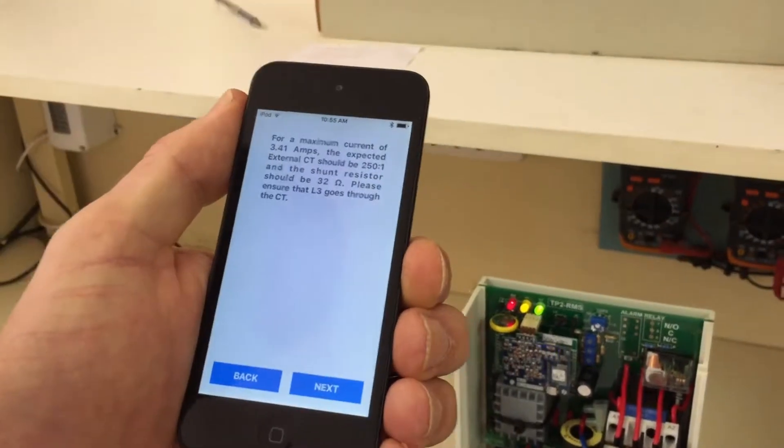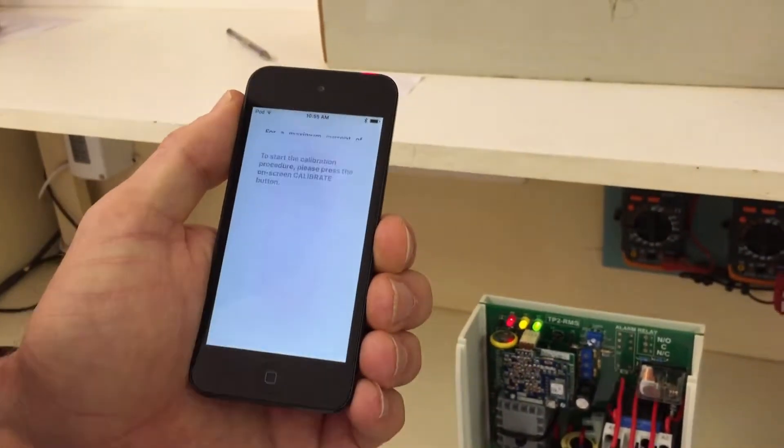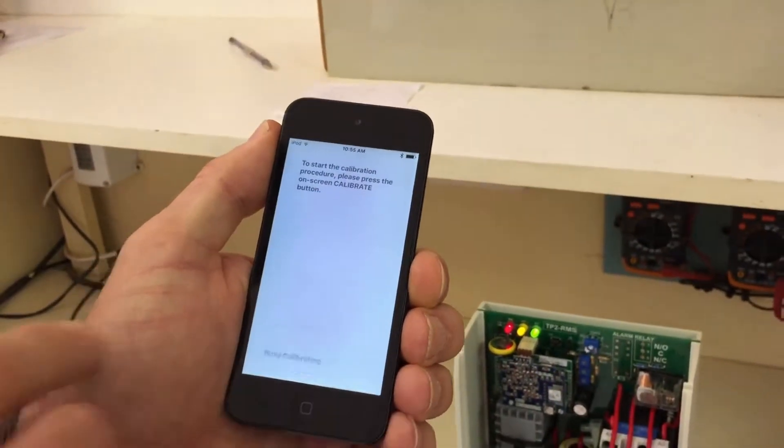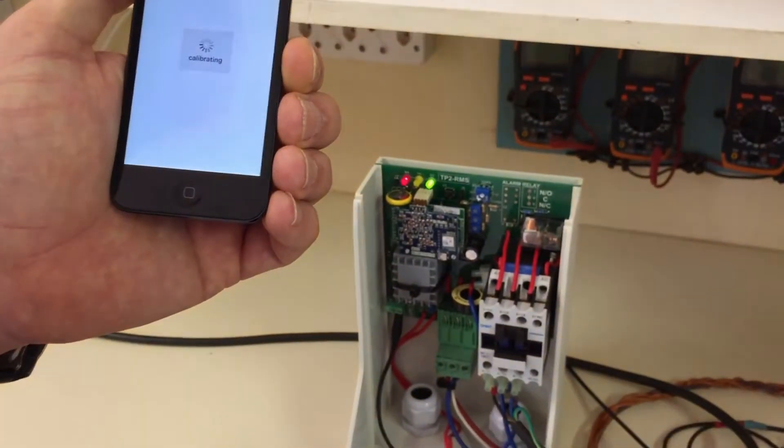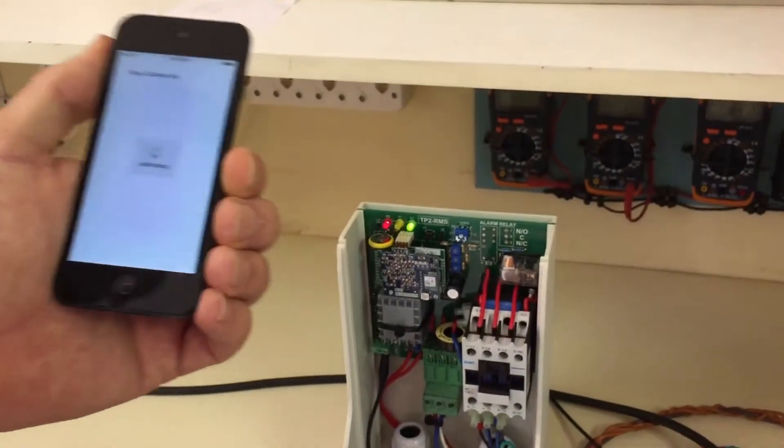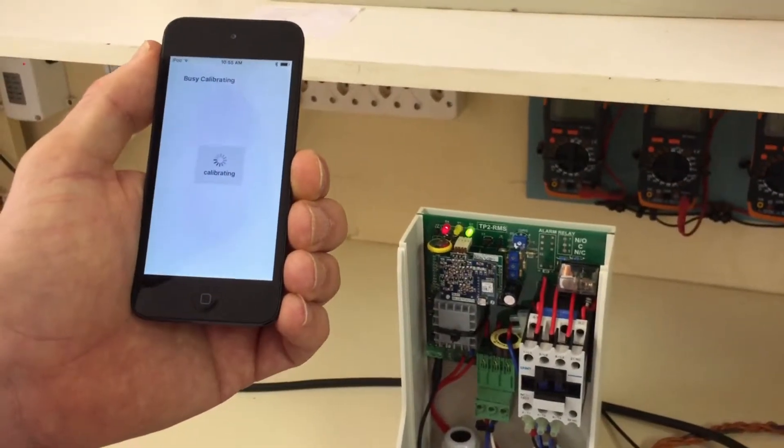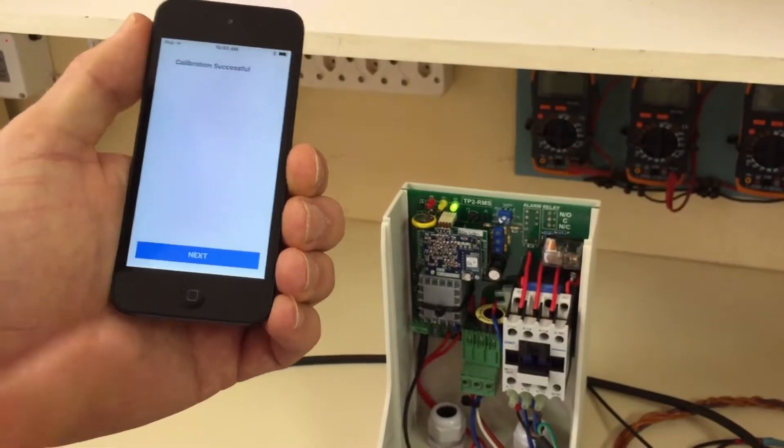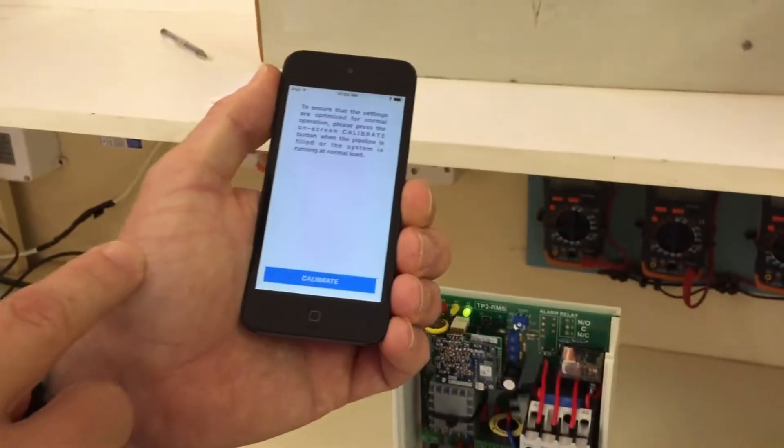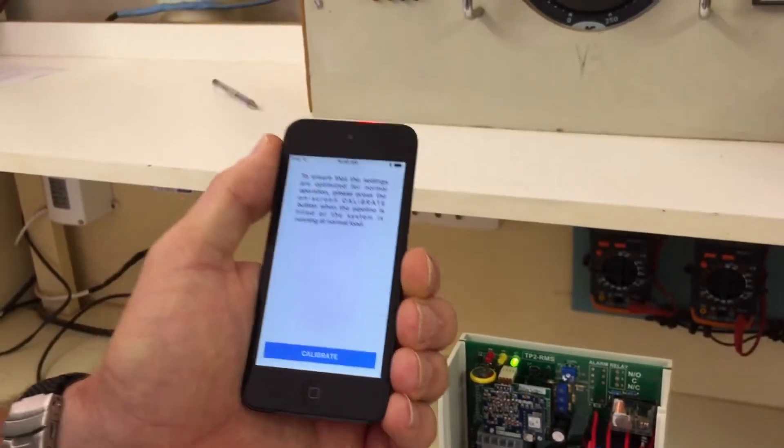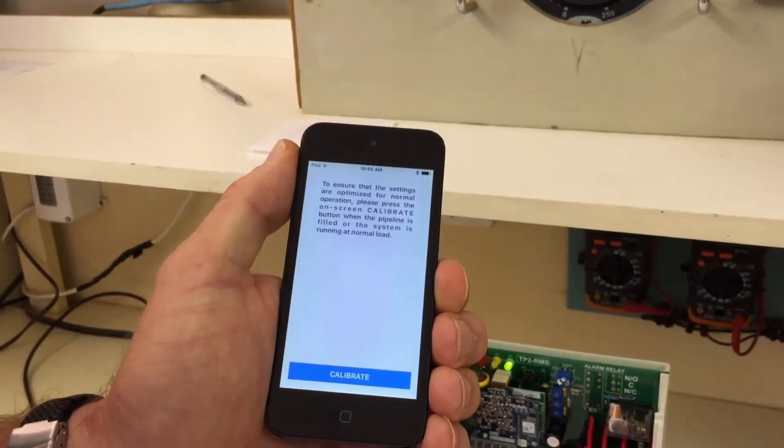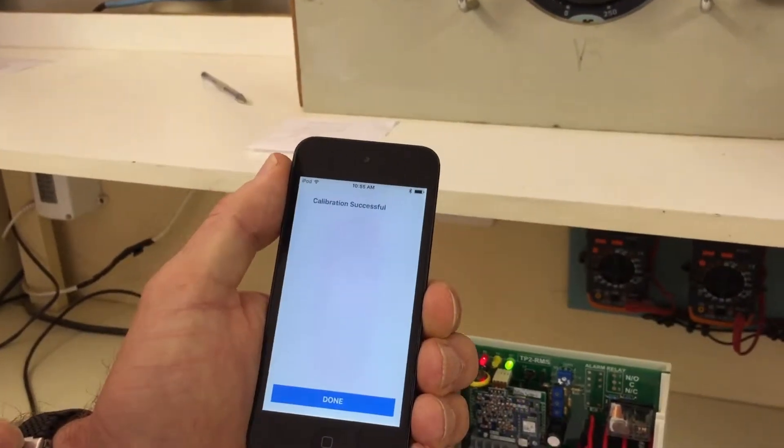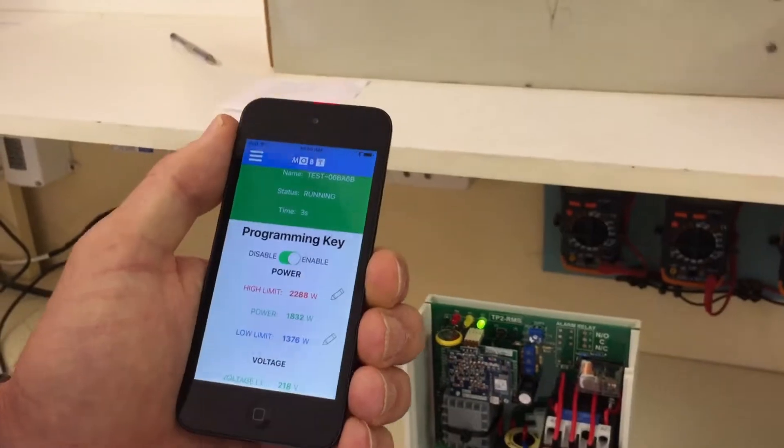Just more information for the shunt resistor on the CT, on the bigger models. To start, press the calibration button. It starts, checks if the current is not above the limit. Press the next button. It will then prompt you to wait until the pipe is full, because then the load on the motor is going to change. And you do a new calibration then. Calibration successful, done.